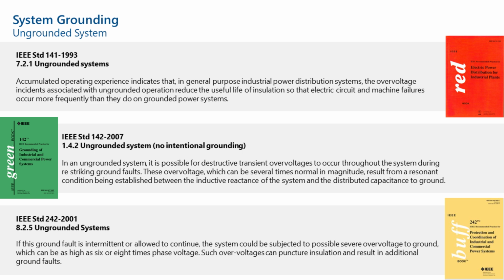So what do the standards say about ungrounded systems? The Red Book says that accumulated operating experience indicates that in general purpose industrial power distribution systems, the overvoltage incidents associated with ungrounded operation reduce the useful life of insulation. Yes and no. I would think this is a problem more above 5 kV than below 5 kV.